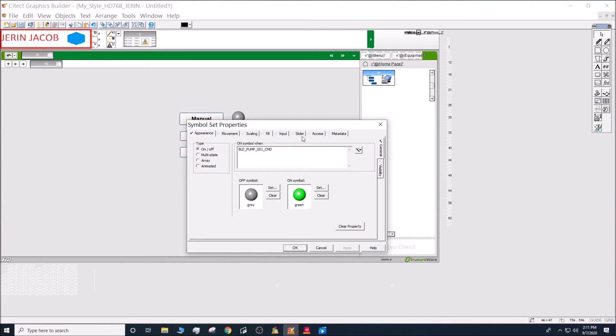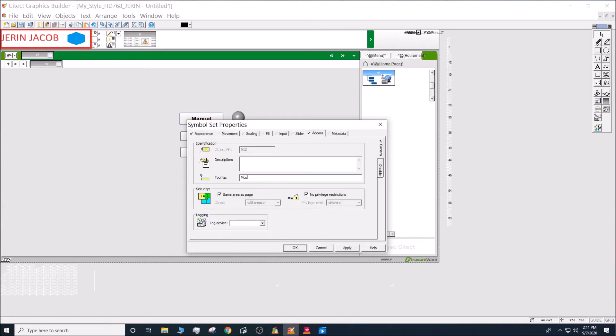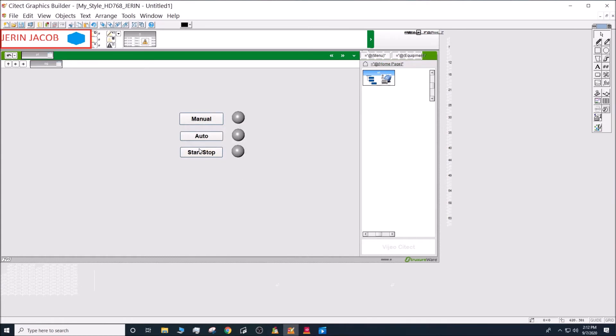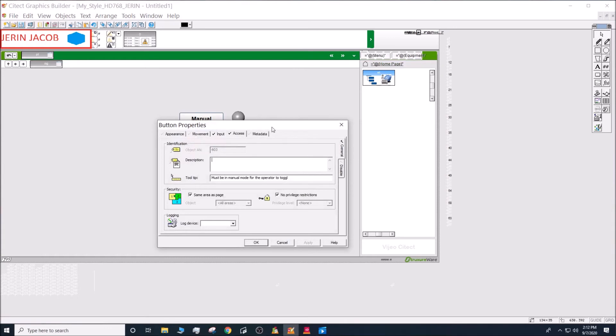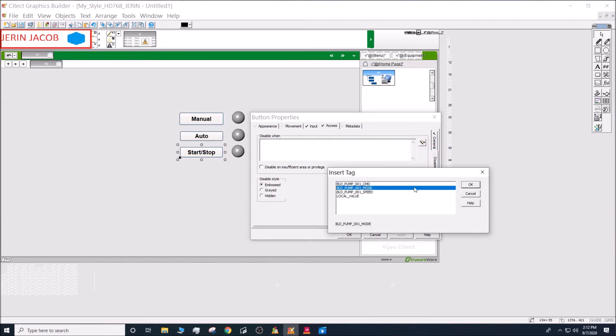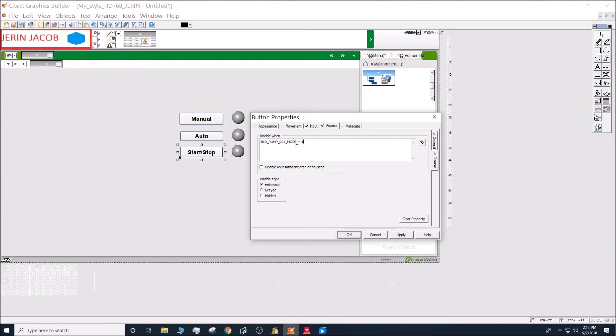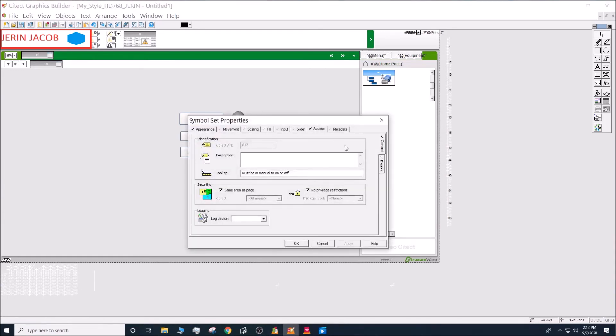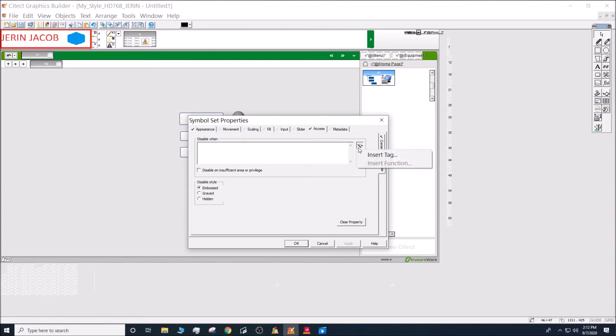In the same way, go into the LED symbol, go to Access and give it a tooltip such as 'Must be in manual mode'. We also want to disable the start/stop button and the LED when the pump is in auto mode — that means disable when the mode tag equals one.